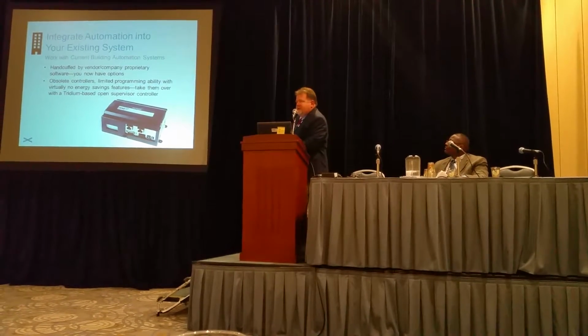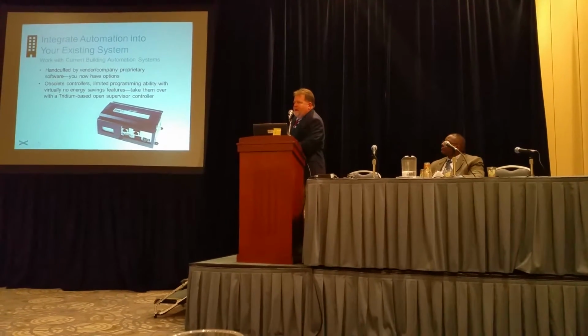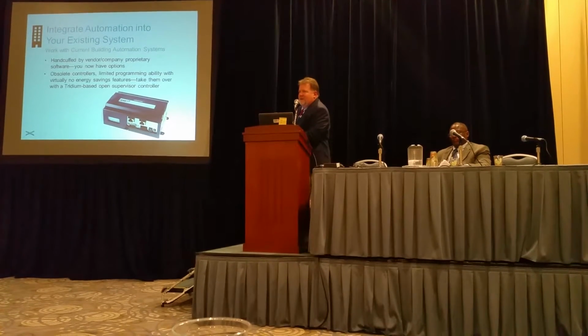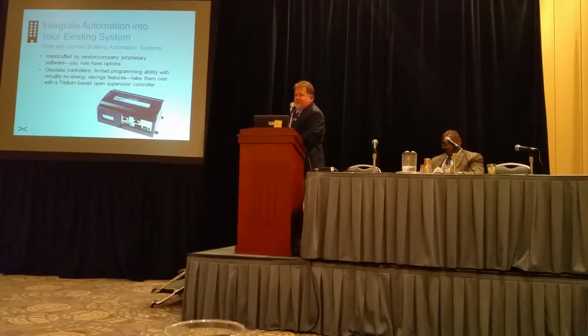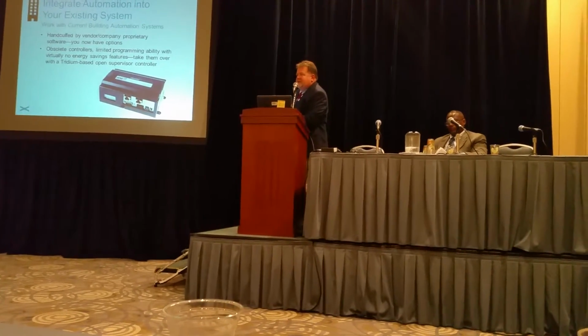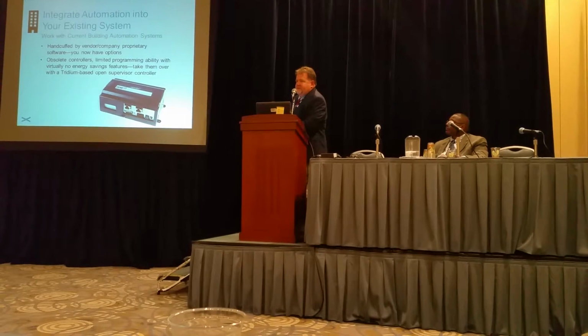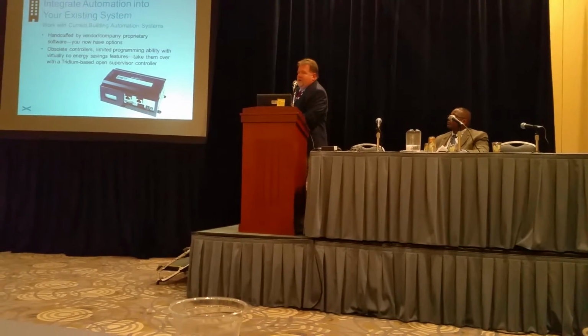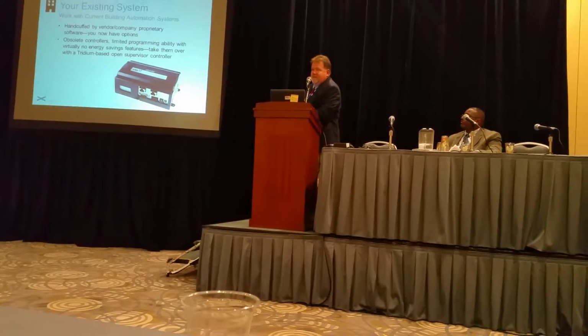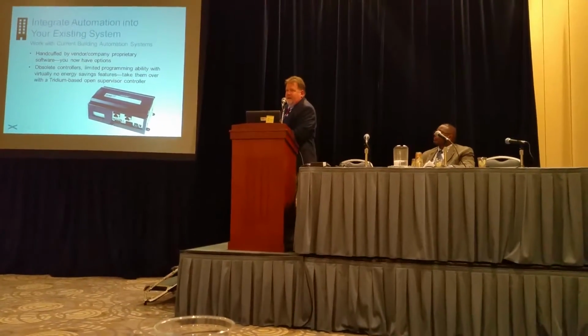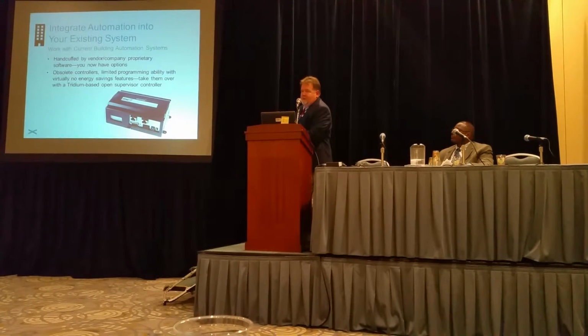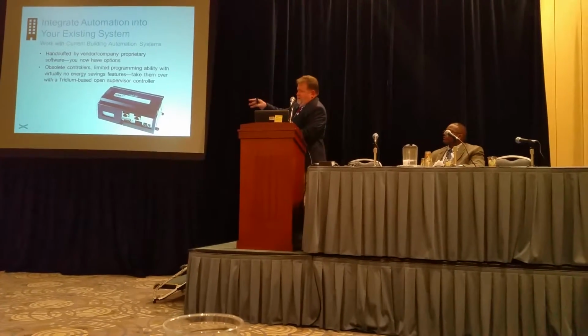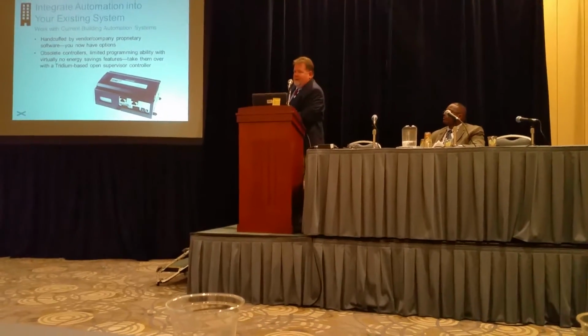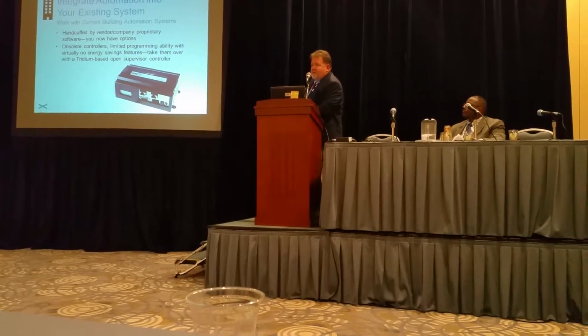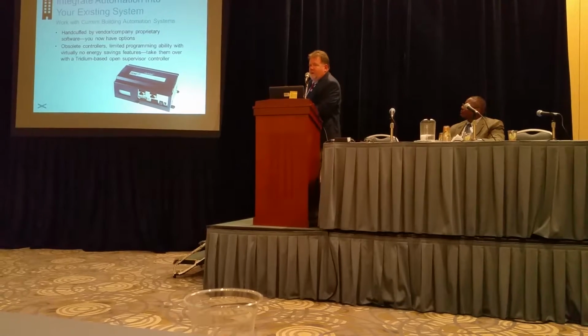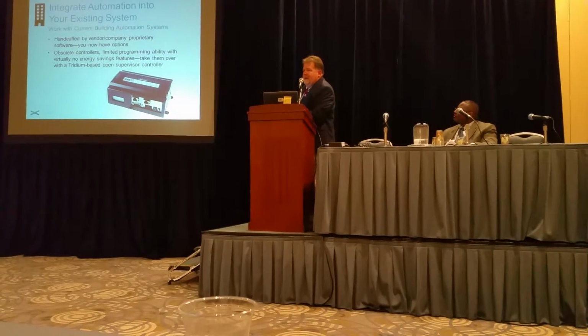The other thing about the Tridium system that makes it so appealing is if you remember back in the day when you installed a video card in your computer or a new monitor, you'd have to install drivers on the computer to communicate with it. It's the same thing with this. So if you had a different manufacturer system, say it's a Johnson Metasys system, you would install an N2 driver to communicate with the Johnson Metasys network. If you had Carrier CCN, you would install the Carrier CCN driver on the Tridium box to communicate with that. If you had a building that had Carrier, Johnson, whoever else, we can communicate with all three of those on 3 separate networks. So it's really nice to be able to add a driver to a robust front end like this that's non-proprietary and be able to control it.